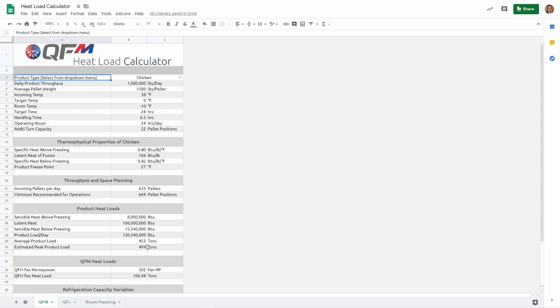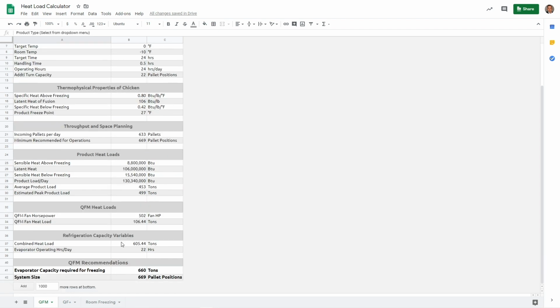And then we have a little bit of buffer here for estimated peak product load. So this is trying to help maintain room temperature if there's a large spike in the loading of several warm loads into the same area. We want the refrigeration system to be able to respond and maintain room temperature. So a little extra capacity is suggested there. We then add all the watts from the QFM units, and then we have a combined heat load.